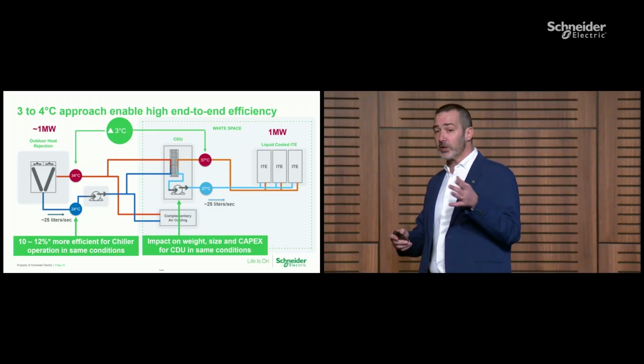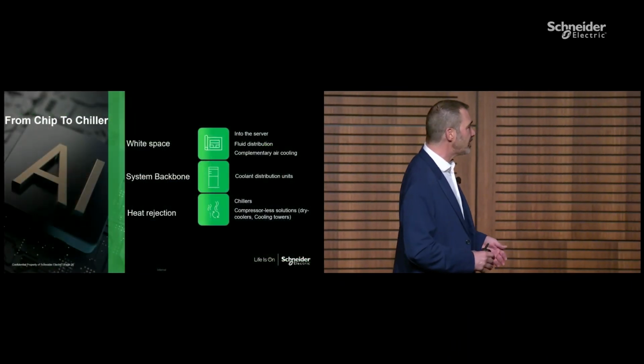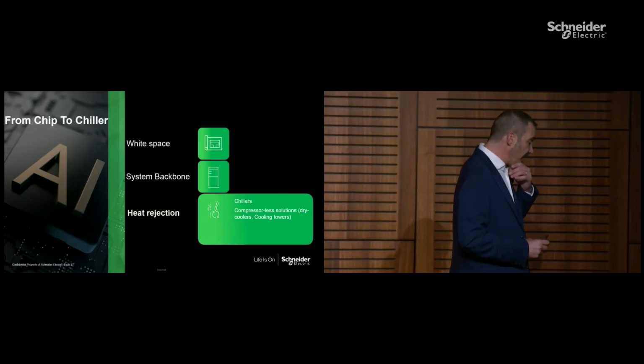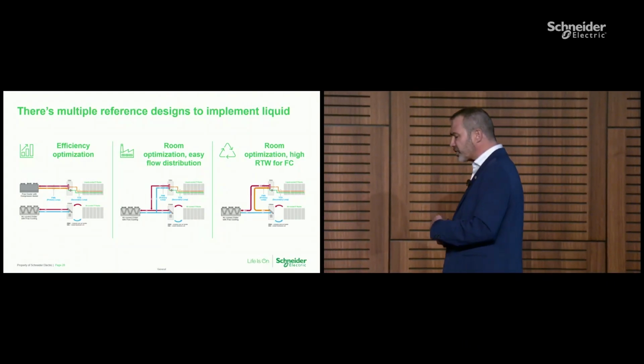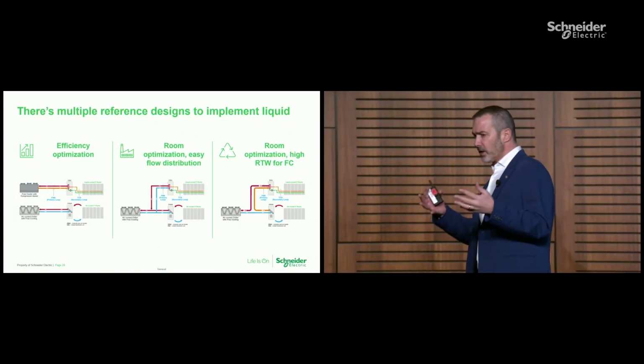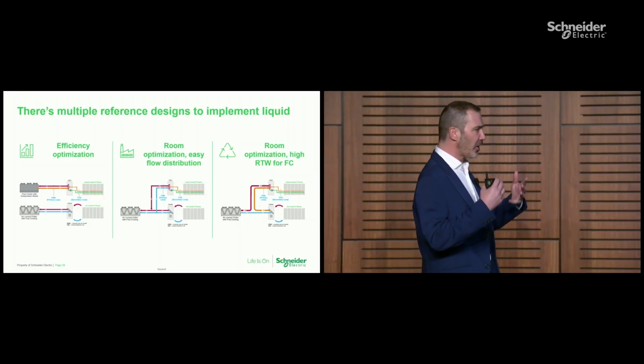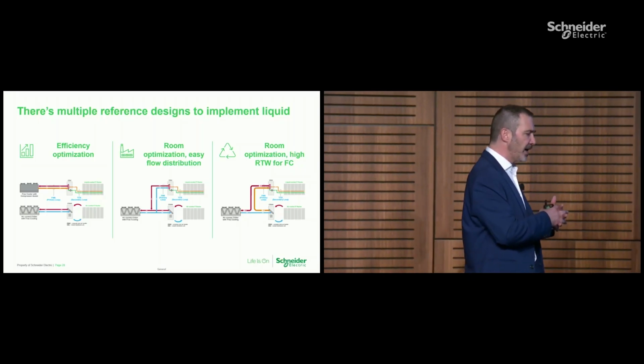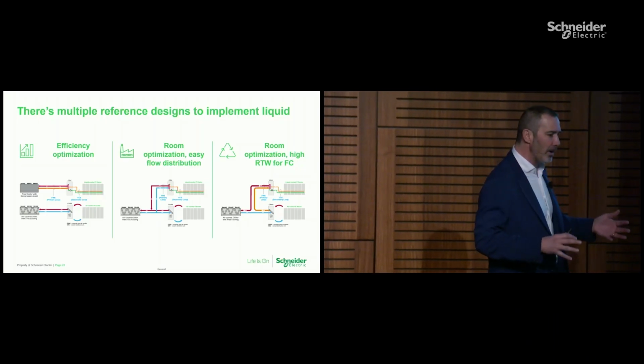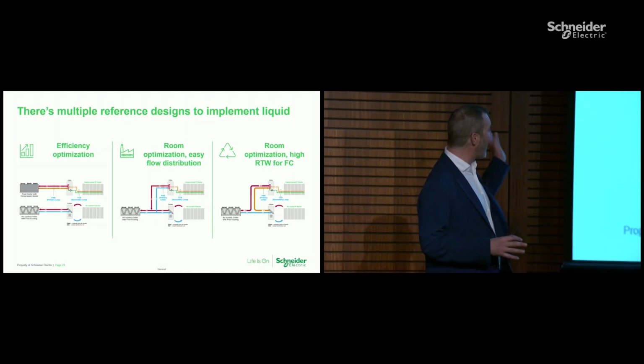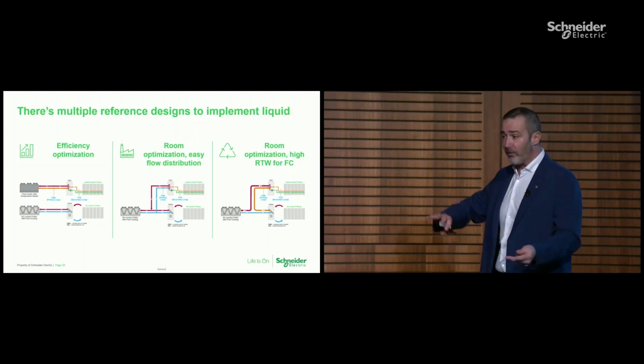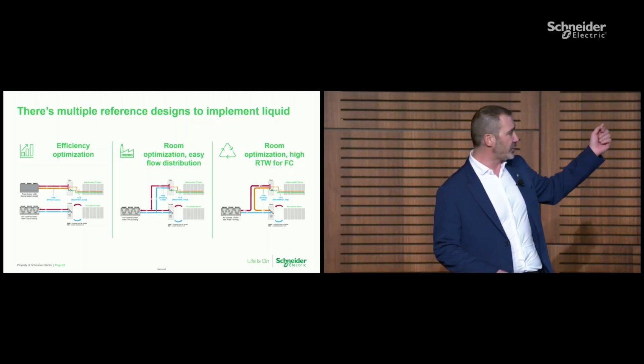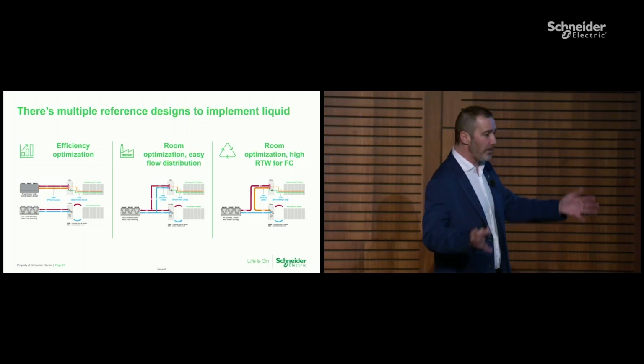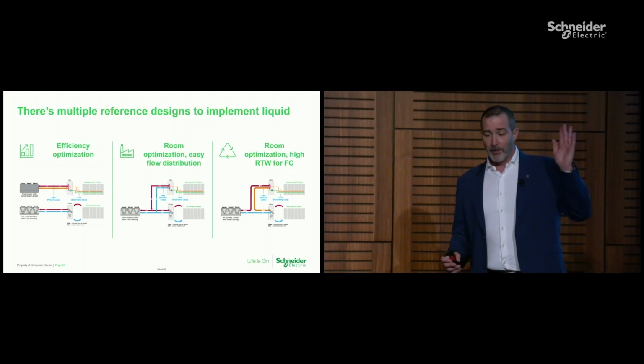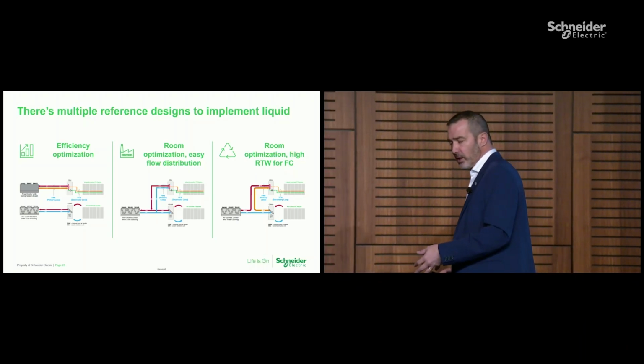And looking at the big elephant in the room, let's move to the final portion of that. So what about the heat rejection unit? And what about the chiller outdoor? Or which kind of chiller do you need outdoor? There are several different ways to combine the heat rejection with the CDU and the CRAH. Those are a few examples. We have a reference design you can download from our website where you can combine the different solutions. However, regardless of the technology you are looking at, if you have two chillers, one for liquid cooling and one for air cooling, or the same chiller with the same loop, or the same chiller with a series loop, regardless of this, the main driver is what is the temperature for the server.